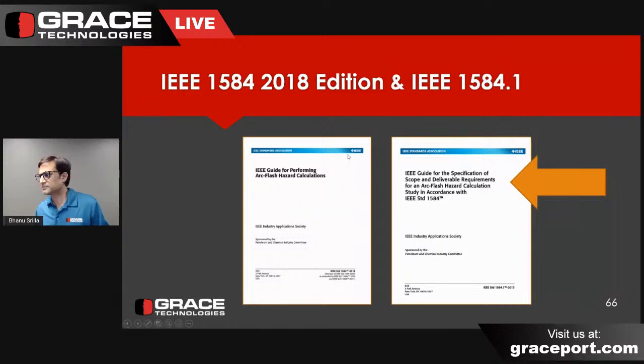So incident energy calculations can go up and incident energy calculations can go down slightly, all right? So the VCB and the VCBB box electrode configurations, well, and VCBB is new. It's a new box electrode configuration in the 2018 edition of 1584, right? Again, they yield calculations that could be lower than the old VCB, but HCB will be potentially slightly higher, right?